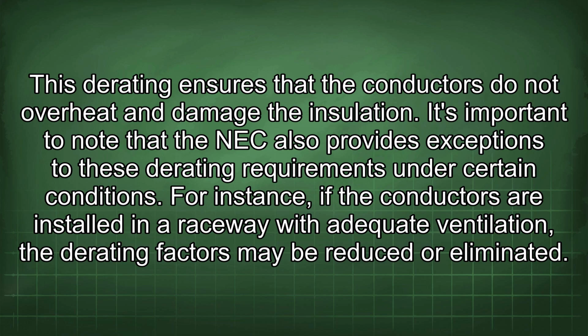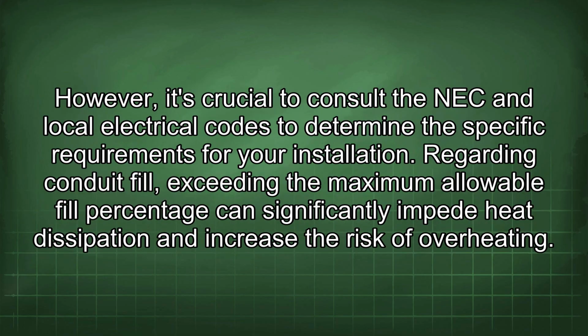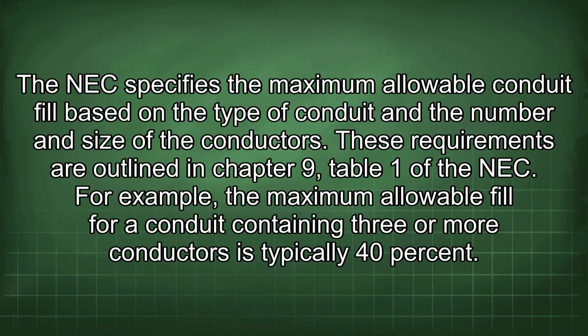It's important to note that the NEC also provides exceptions to these derating requirements under certain conditions. For instance, if the conductors are installed in a raceway with adequate ventilation, the derating factors may be reduced or eliminated. However, it's crucial to consult the NEC and local electrical codes to determine the specific requirements for your installation. Regarding conduit fill, exceeding the maximum allowable fill percentage can significantly impede heat dissipation and increase the risk of overheating. The NEC specifies the maximum allowable conduit fill based on the type of conduit and the number and size of the conductors. These requirements are outlined in Chapter 9, Table 1 of the NEC.